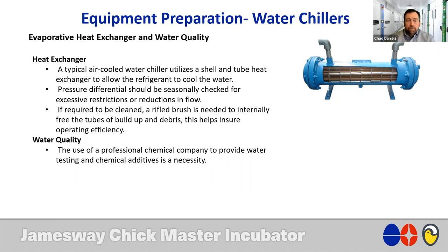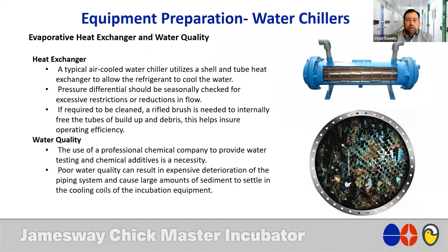And so with that, you'll generally find in chillers that the water quality is really very bad. If you have this bad water and you pull the end off of this shell and tube heat exchanger, oftentimes this is the image you find. A lot of debris, a lot of stuff that's in the water, and water can't flow through these little tubes any longer. And so we've lost a lot of our efficiency with our cooling, and we've lost a lot of capacity. So we're wasting energy and we're not managing our room conditions when that's the case.